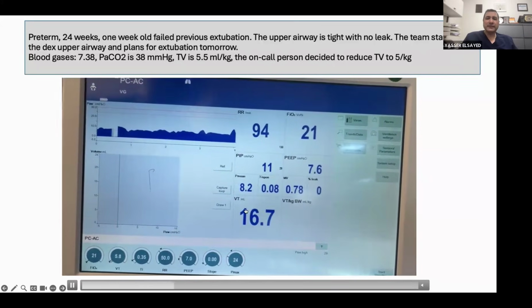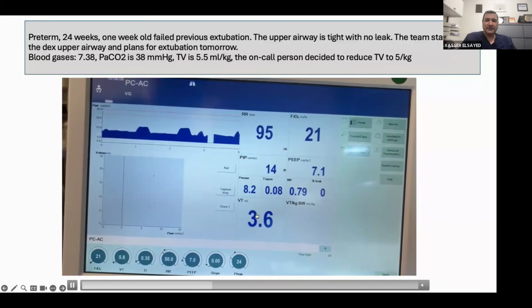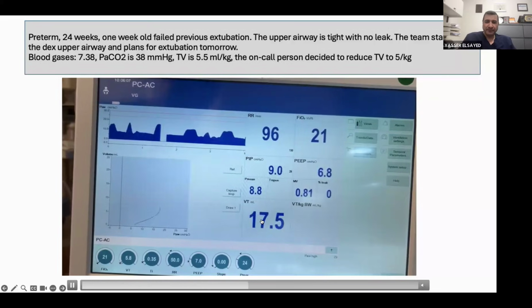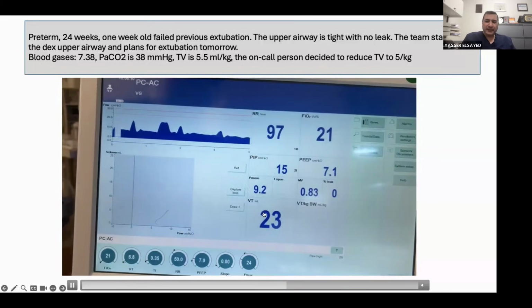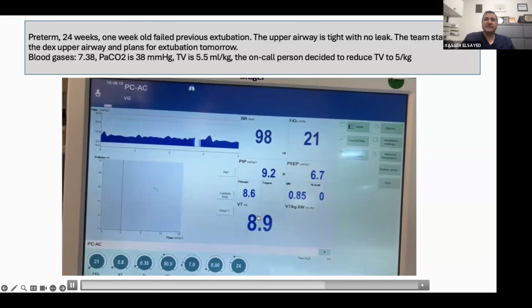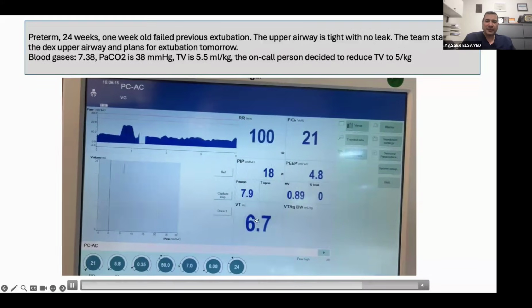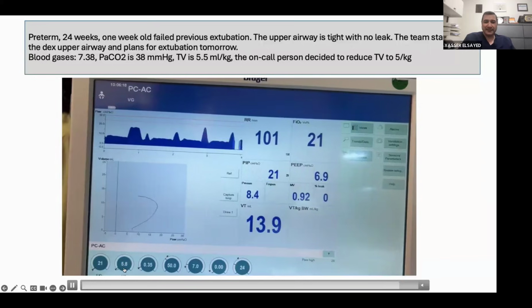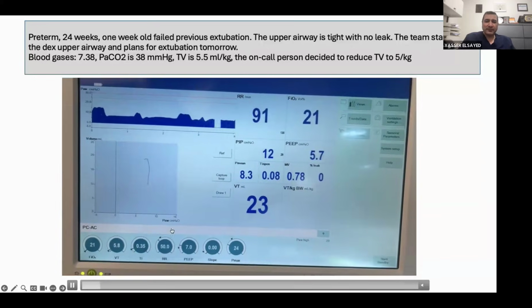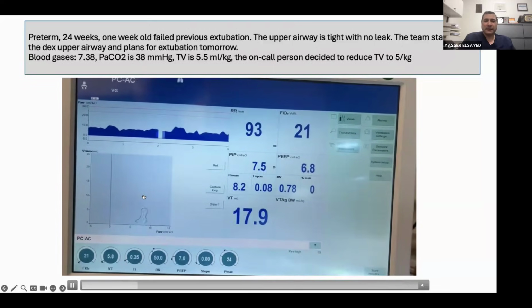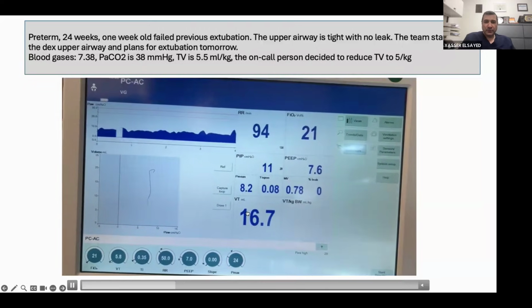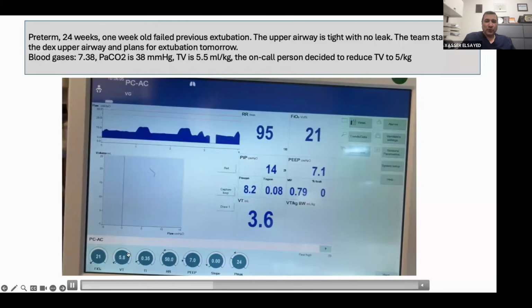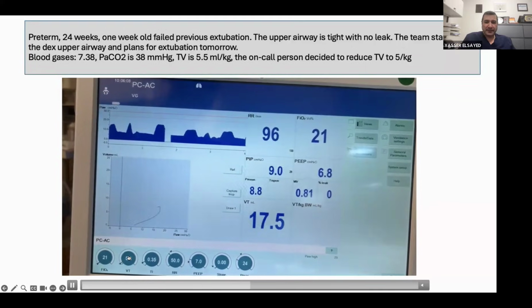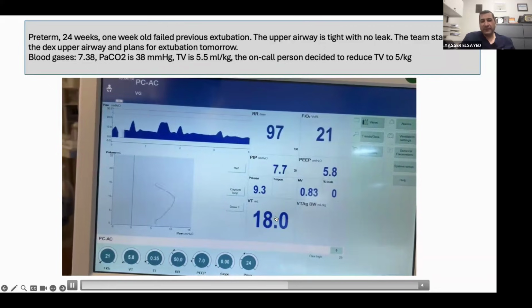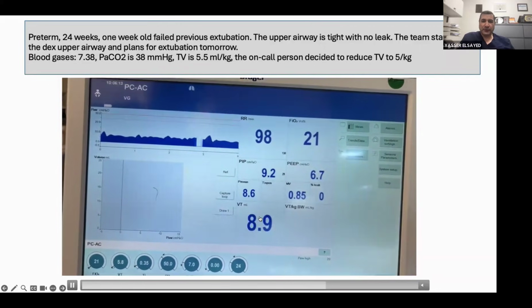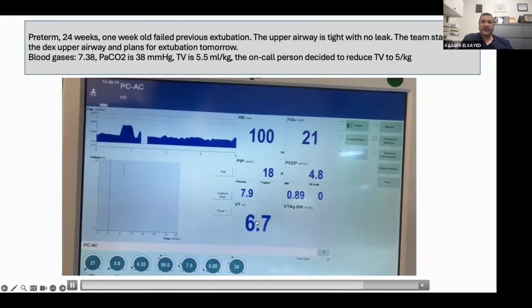If the patient is trying to get a higher measured tidal volume, it means that the patient is trying to breathe higher because of good compliance. But each time he's trying to breathe higher, the machine tries to lower the PIP to bring this number down to match the preset. When the machine is trying to do that, because the preset is low, the infant will be in air hunger. So again, when you lower the preset tidal volume, but the infant is trying to breathe a higher tidal volume because of good compliance, the machine will try to bring the number down.